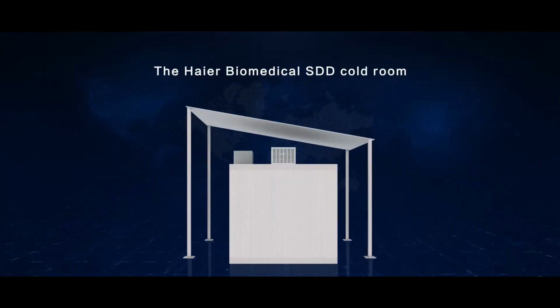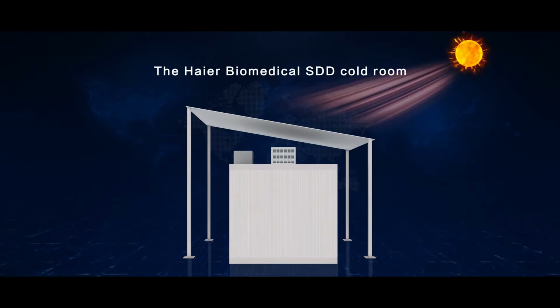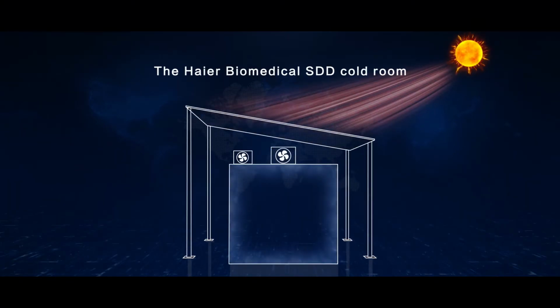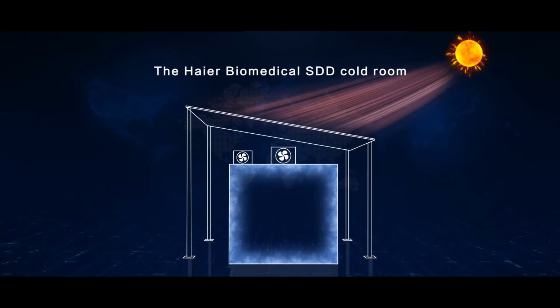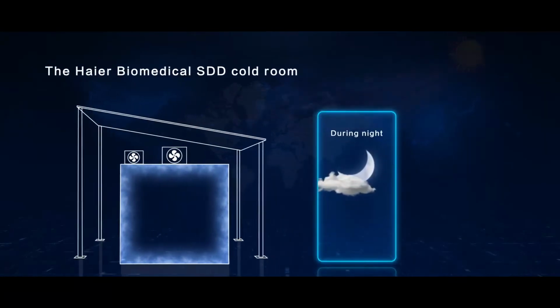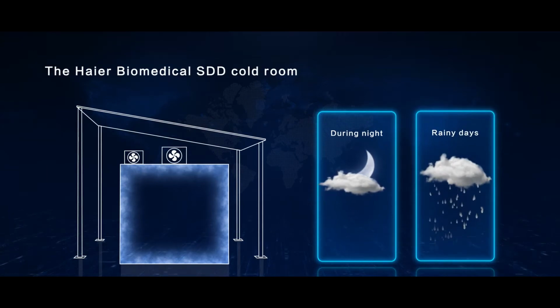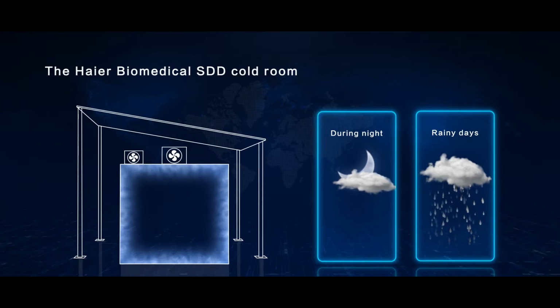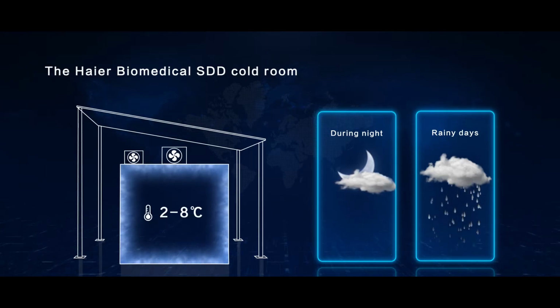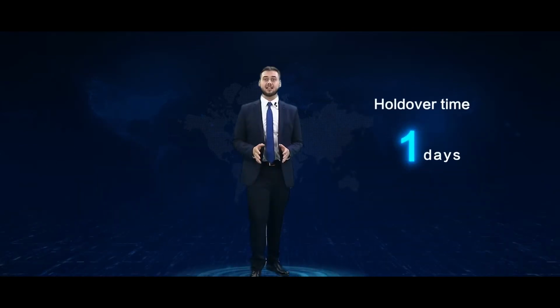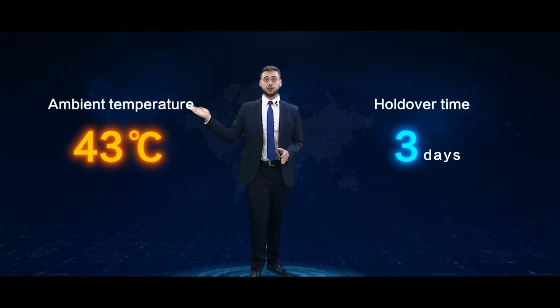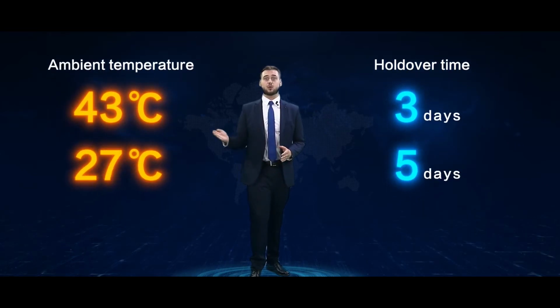The Haier Biomedical Solar Cold Storage Room utilizes ice thermal energy storage technology and uses solar energy to produce cold storage capacity. Even if there is not enough light during night or rainy days, the frozen ice in the water tank will slowly release its cold energy to ensure that the temperature in the cold room can be maintained at 2 to 8 degrees Celsius. Its holdover time is at least 3 days at 43 degrees Celsius and 5 days at 27 degrees Celsius. Even if there is a failure in the cold room, there will be enough time for troubleshooting.